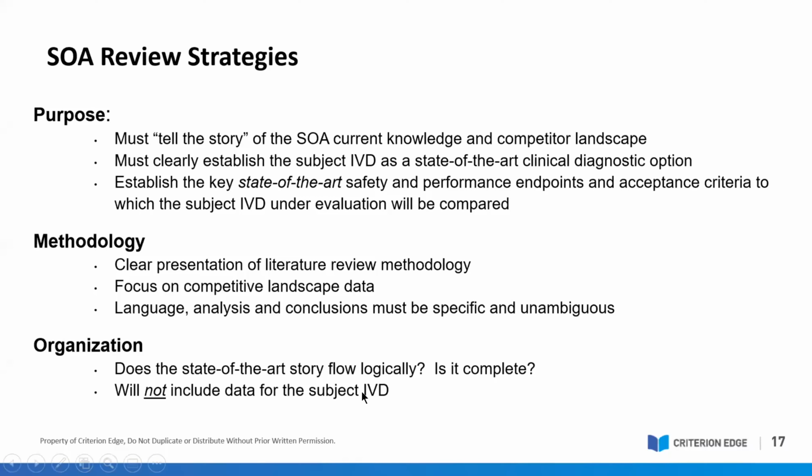The state of the art is really a core element of the essential requirements of the IVDD, and it remains so as part of the general safety and performance requirements for the IVDR. In IVDR Annex I, they stipulate that the device shall be designed and manufactured in such a way that it is suitable for the purposes as specified and suitable with regard to the performance it is intended to achieve, but also taking into account the generally acknowledged state of the art. So that's where the whole point of the state of the art comes in.